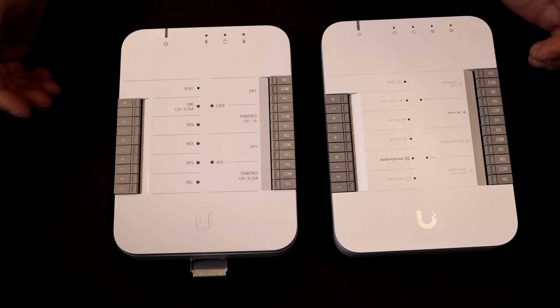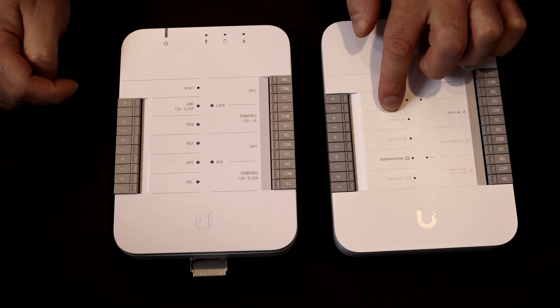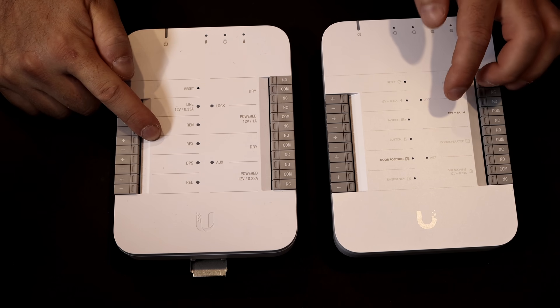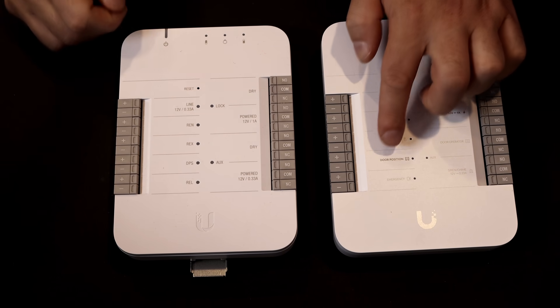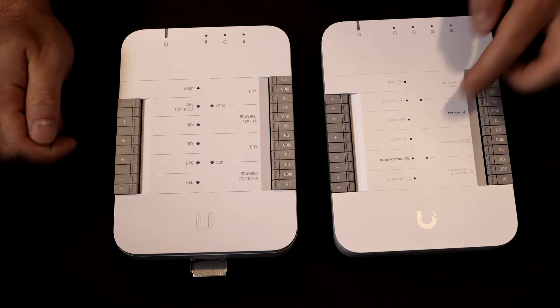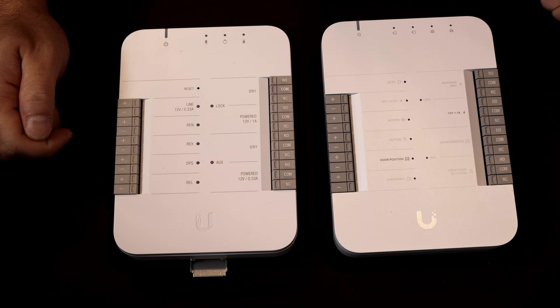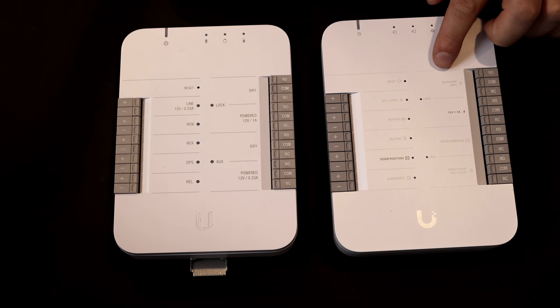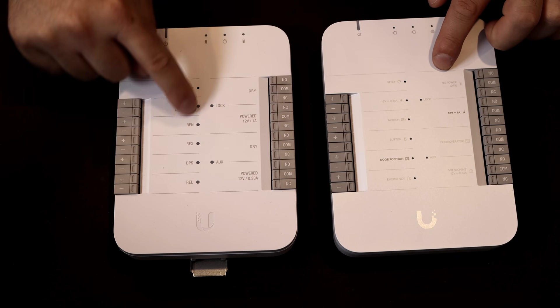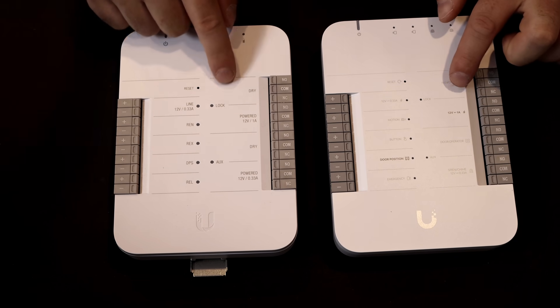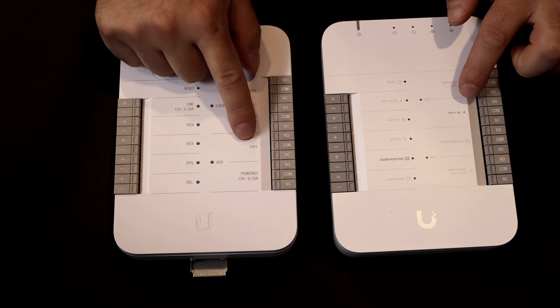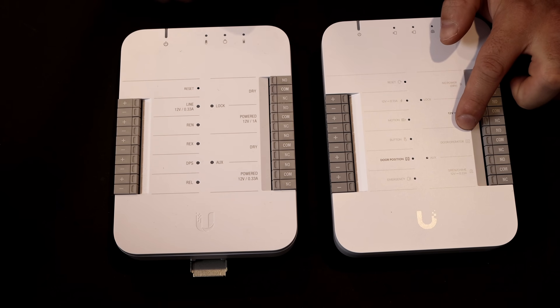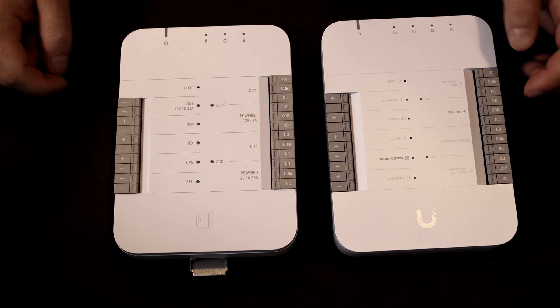Below that, the naming convention has just changed. This one says run, and this one says motion. We have our REX, which would be our request to exit, but on the new one, it says button. And then we have our DPS, or we have our door position switch. On the very bottom, this one says release, and this one says emergency, so if we're tying into a fire alarm panel. On the top right, we have dry, and this one says no power, and then we have this lock. So these are all LEDs, and they light up when you put your conductors into the hub. Below that, we still have our 12 volt 1 amp powered, and then we have our dry, but this one says door operator. And then at the very bottom, we have our powered 12 volt point 33 amp.